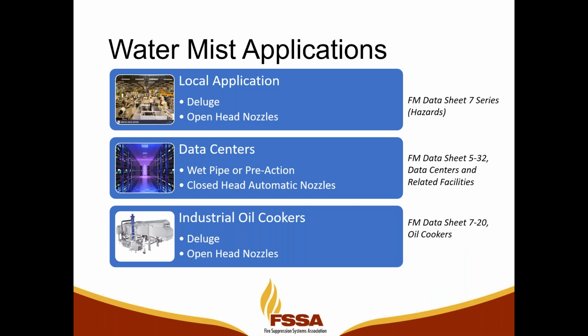Water mist is also used in a local application format, and FM's got a specific testing protocol for local app. CO2 is also used in local app. Those are really the two agents that we can use to protect a critical asset that sits within a larger space. So rather than protecting the entire room, we're protecting a hazard within the room. So when we do that, we arrange a grid of nozzles on all open sides of the hazard, and we're going to direct our flow of water mist through all nozzles simultaneously, so it's a deluge system, and we're going to hit that hazard from all sides with water mist. And FM's got a whole series of data sheets, Series 7, that cover the different local applications.